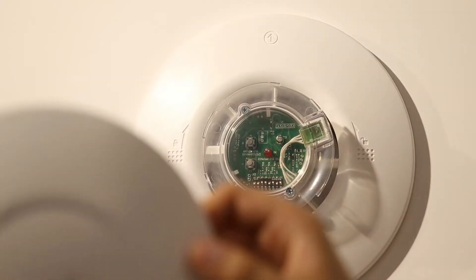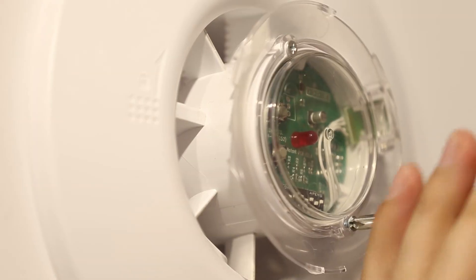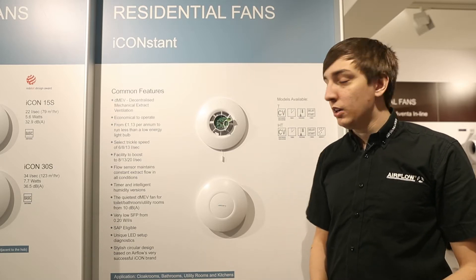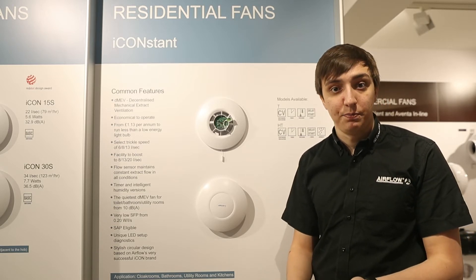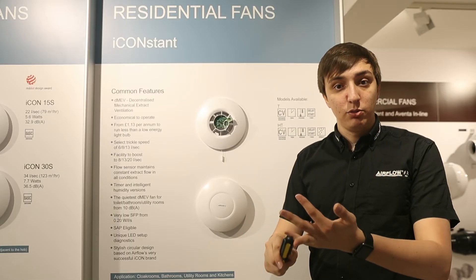To adjust all of these settings, you'll need to remove the front cover of your iCONstant. This can be done by twisting the cover and pulling it away. You'll then see the IPX cover, which is retained with two Phillips head screws that can be removed with a screwdriver. Once the front cover is removed, you can see some of the other great features of the fan. The two buttons can be used to tailor up or down the flow rates to get the flow rate required for your installation. The red unique LED indicator is there for diagnostics and installation purposes, flashing in different patterns for saving settings or if there's an error with the fan. At the bottom is where all the settings for timer, humidity, and the flow sensor can be adjusted using different combinations, which can be found in your installation guide.